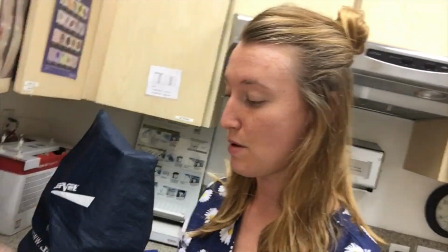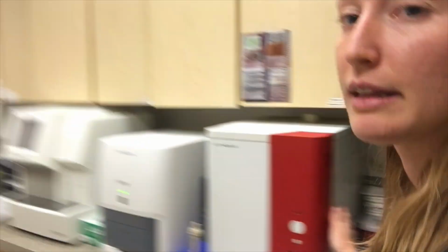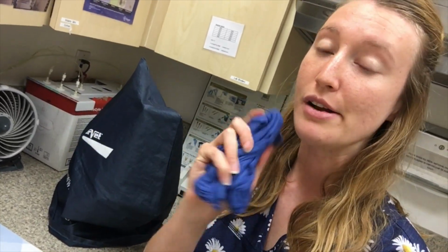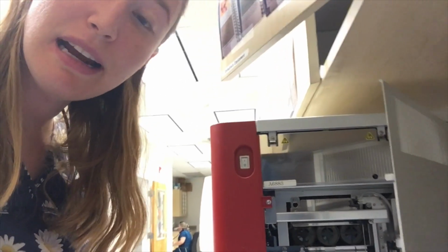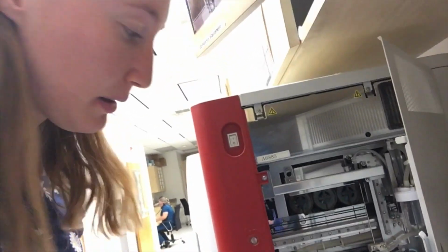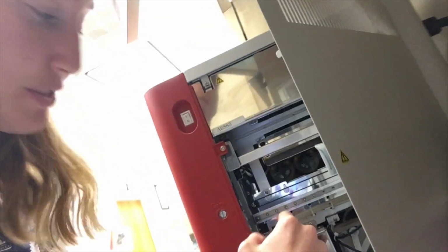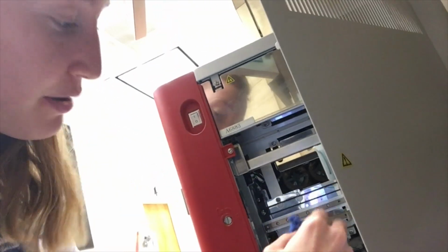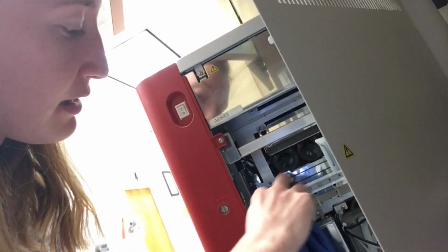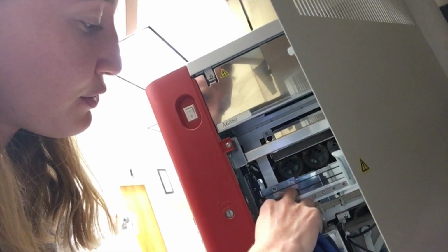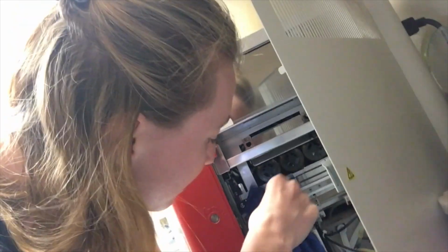So to do this, you want it off, and then I'm going to open up this side door right here. I'm going to clean down the inside with a damp, lint-free cloth. Not wet or soaked, but definitely damp. So I'm going to clean outside of the analyzer with this cloth. So the analyzer is going to be right over here, and so I'm just going to get all of this blood residue out of here. So I'm going to very gently clean it off. If it's very greasy, you can use a very mild detergent. I'm being careful not to touch the actual analyzer. So I'm just going to close it up and turn the machine back on.